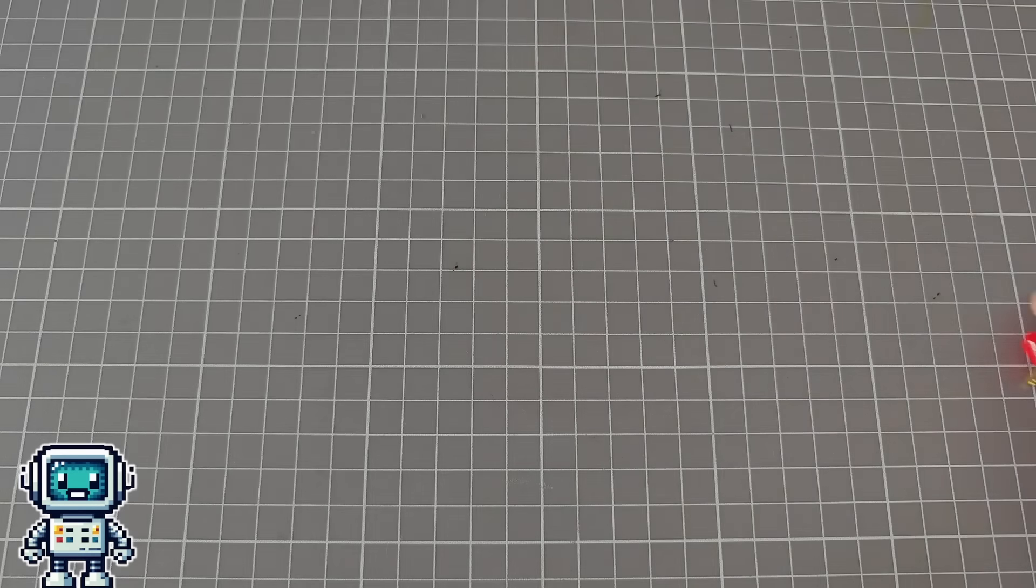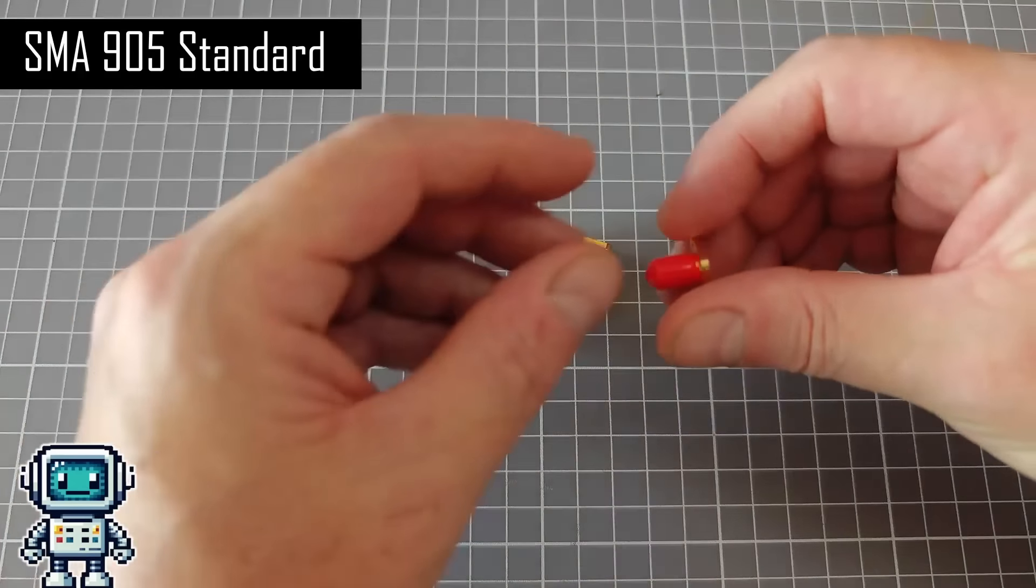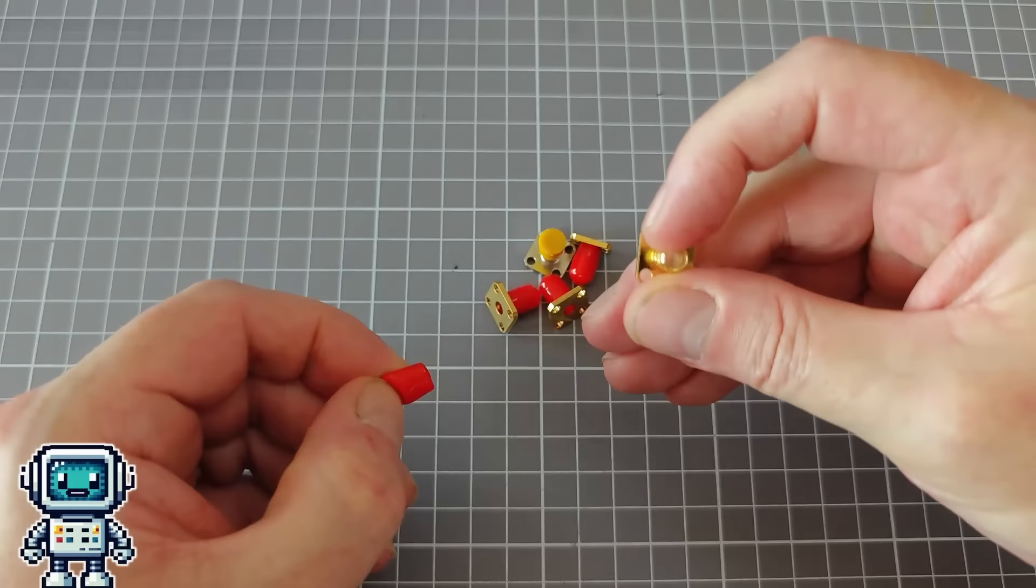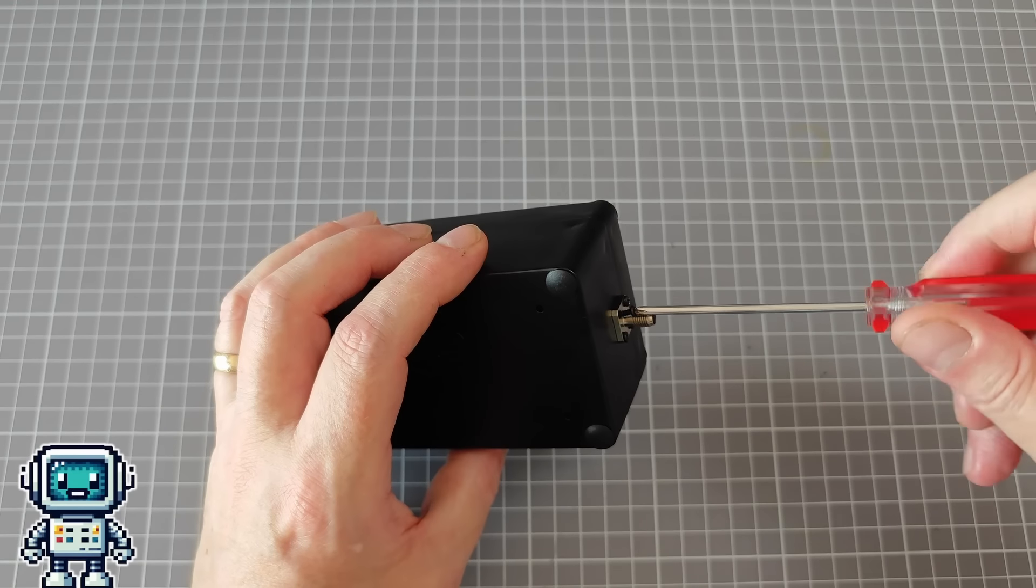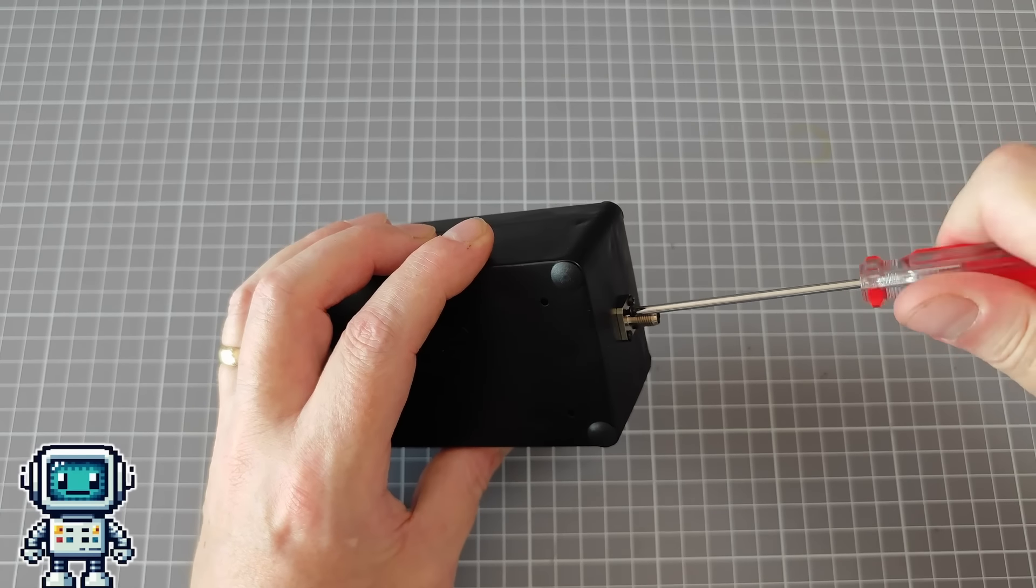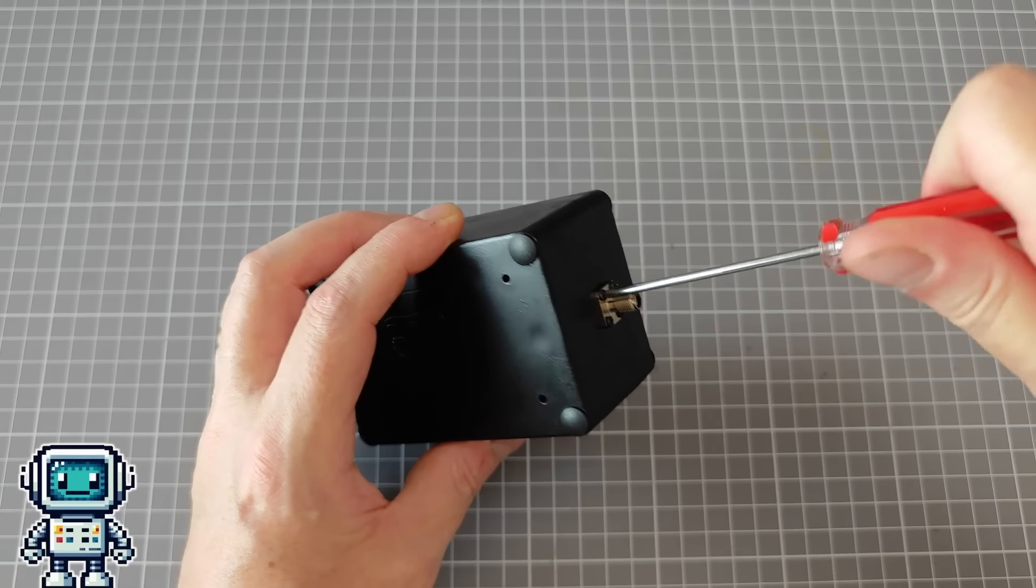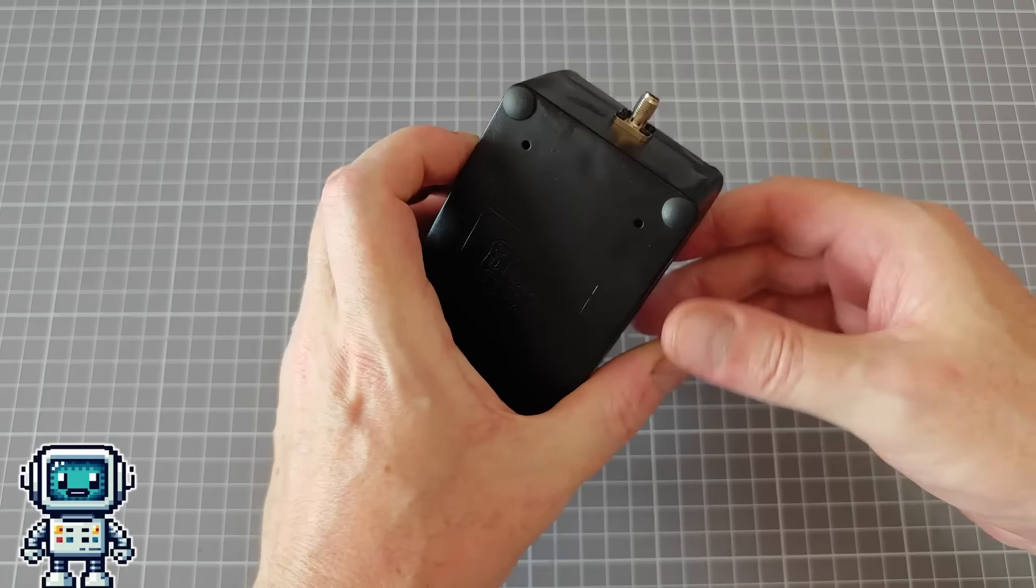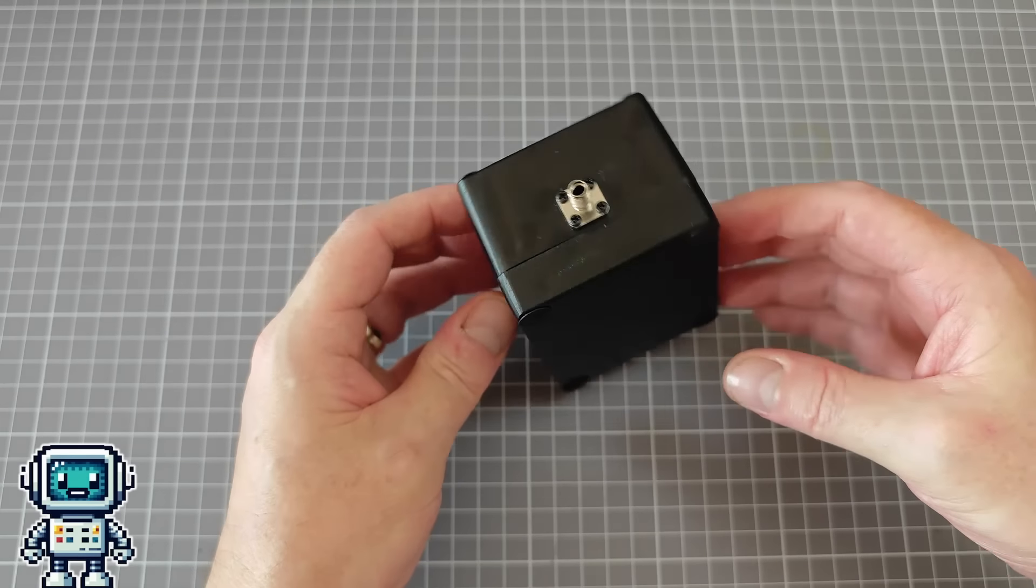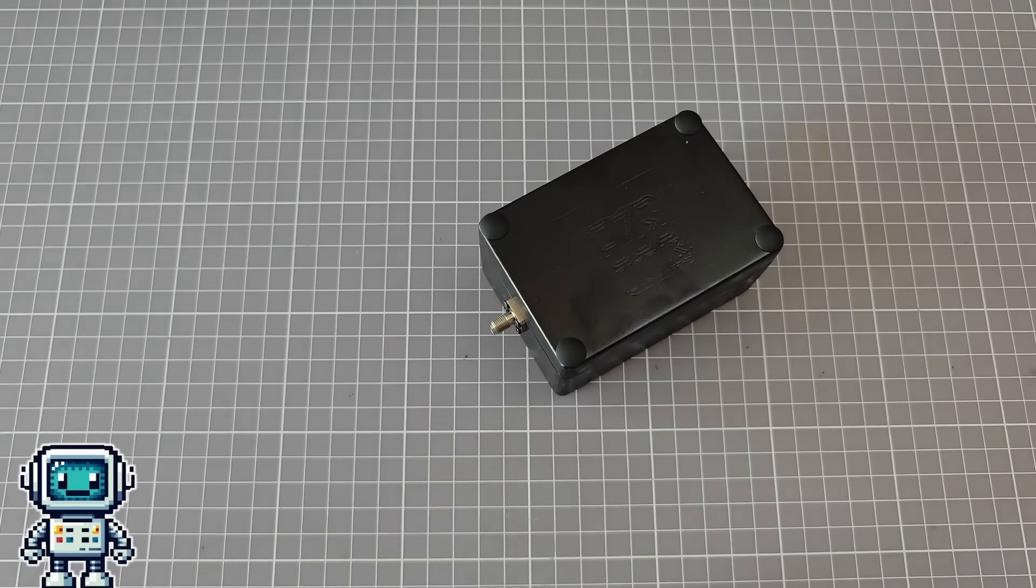We are using the SMA 905 standard for this. It seems to be the most common interconnection standard used for this application. Fitting one of these connectors to the front of the spectrometer could not be easier—just drill four small holes and then screw it to the enclosure. We are not going to delve into this too deeply because later we made a change to the actual enclosure, so let's park this here and move on to the next upgrade we made.